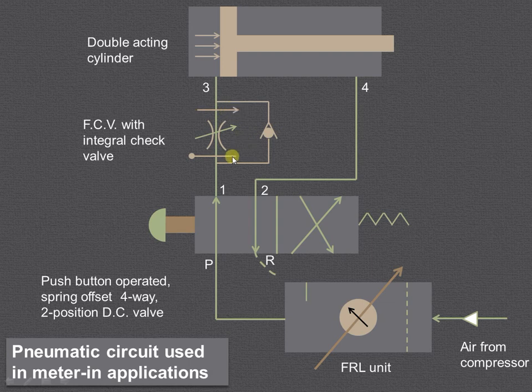This arrow indicates it is pressure compensated, and this is temperature compensated. This is a pressure and temperature compensated flow control valve with integral check valve. This is the double acting cylinder - air can be admitted from both sides.